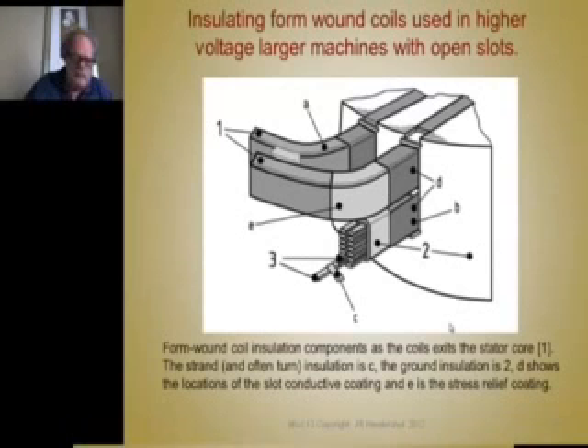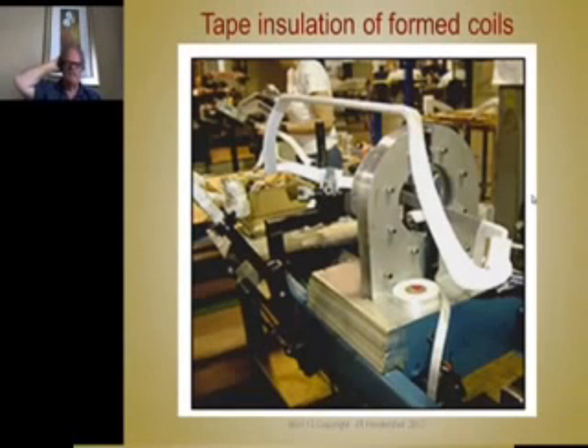Now, the form wound coils: you see how each conductor is rectangular, and each strand is insulated. Each strand is insulated, and then the whole bundle of them is also insulated. This is a machine that does automatic taping of form coils, and these are only inserted in open slot stators. Some of these are 10 feet long, and other ones are only a foot long. So you can tape these by hand, but they have machines that do this.